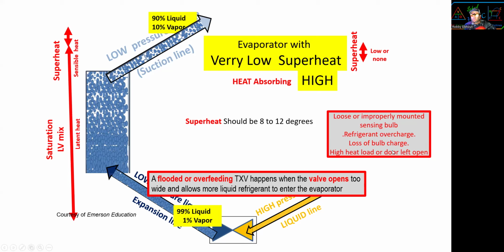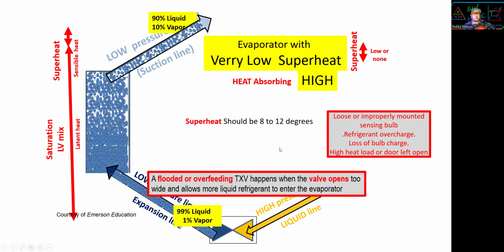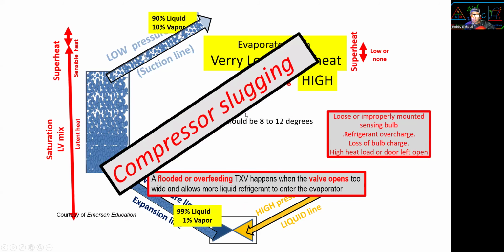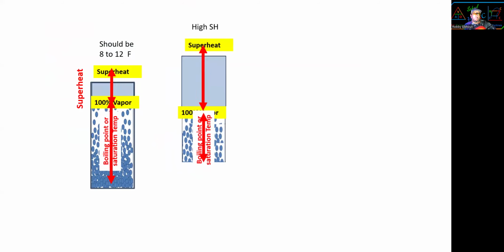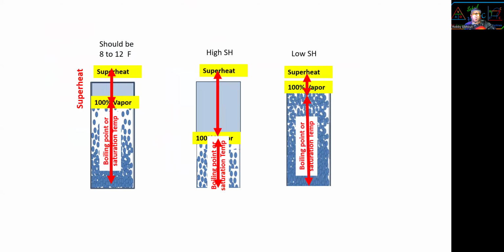High heat load or a door left open will do that too. The compressor will slug, and the whole idea of all this is to protect the compressor. We don't want slugging. All right, so that's how it should be. That's superheat high, superheat low. That's the best way to explain superheat: the temperature differential between the liquid-vapor mist saturation temperature and the superheated vapor exiting the evaporator.